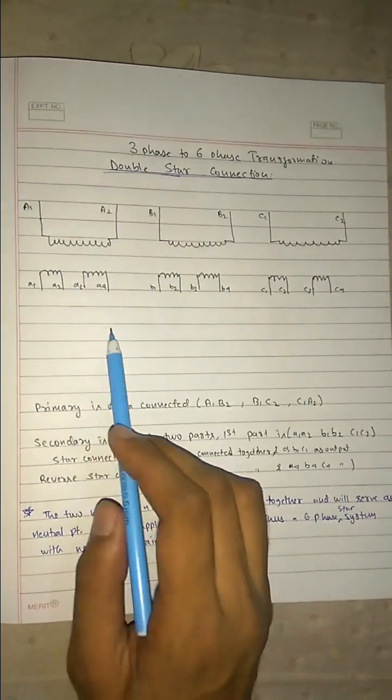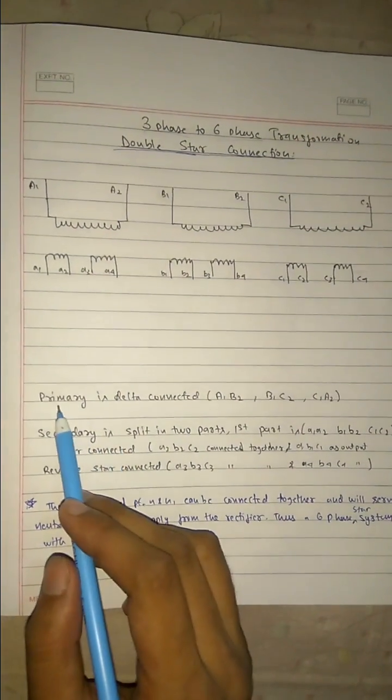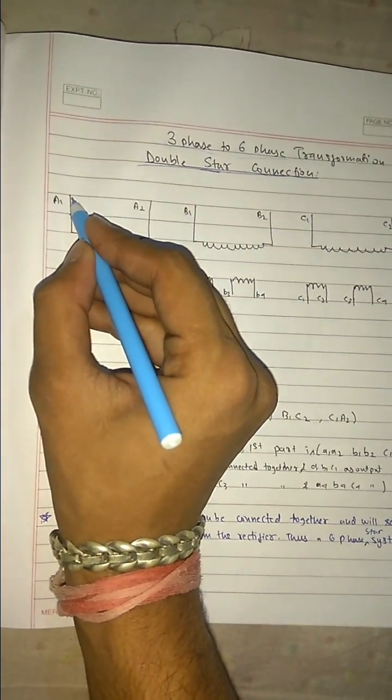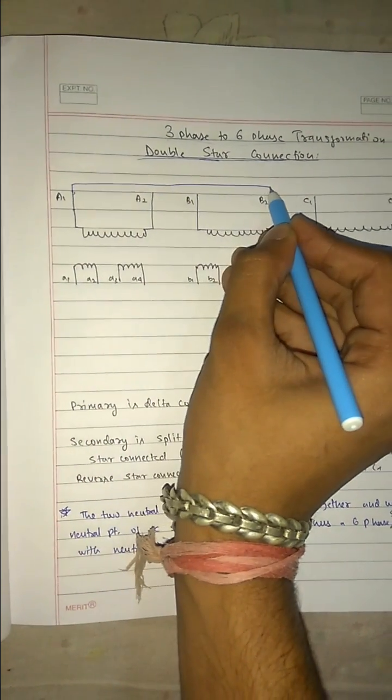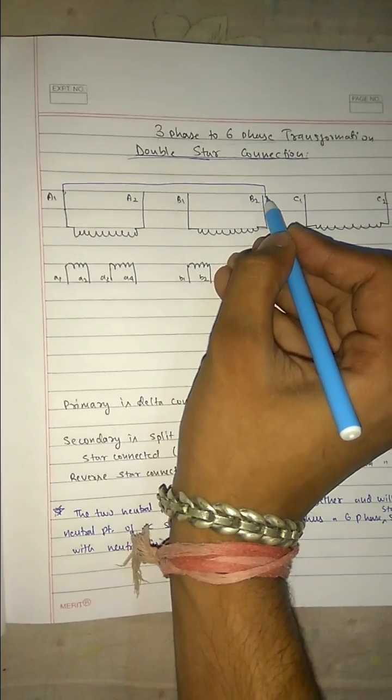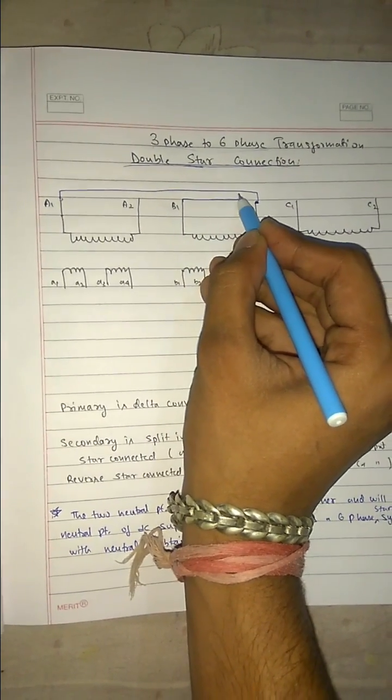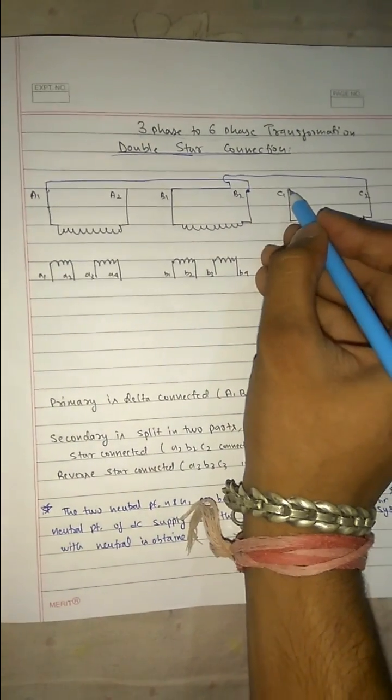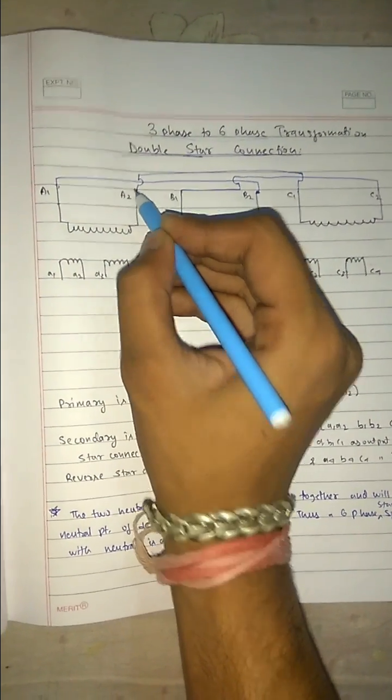These 3 are delta connected and these 3 are star connected. Let's do it step-wise. Primary is delta connected. That is, a1 is connected to b2, b1 is connected to c2, and c1 is connected to a2.